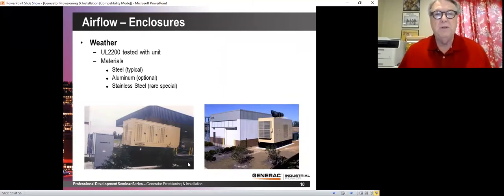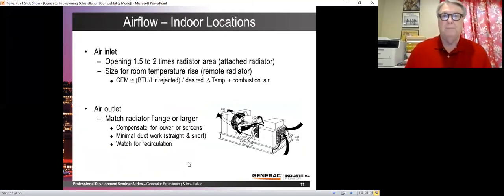So, materials, we typically have steel as the standard material, and with paint systems these days, it generally works very well. If you are near the ocean, you have salt spray, you have corrosive gases, then you may want to go with an aluminum enclosure. Aluminum is typically a higher cost, but in some residential generators, it's simply a standard on that generator. But for the most part, it's higher cost. Stainless steel, rare. I've never actually sold either an aluminum or a stainless steel generator in any significant size, but a stainless steel generator would be a pretty pricey option.